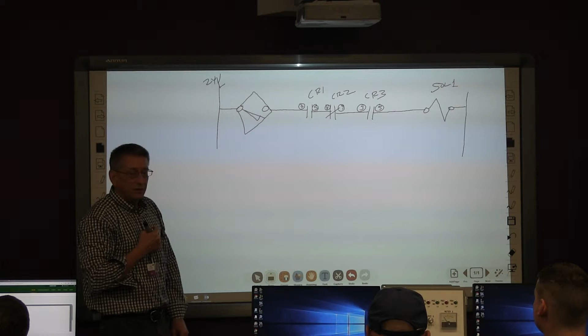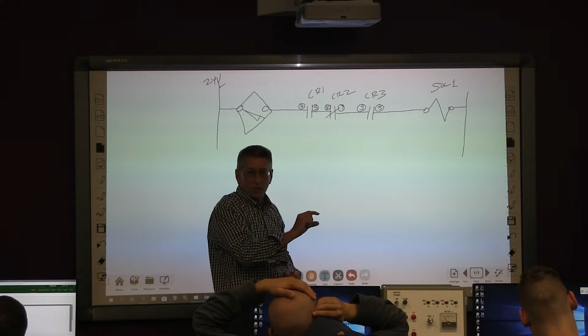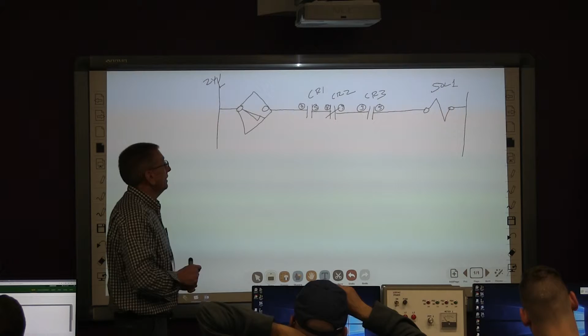Here's the first thing we do. We're already in the electrical panel, right? Where are these relays going to be? In the panel. So you can do a visual observation first - okay, CR3 is energized, you look at it, it's pulled in. Or the light's on if it's a high-speed relay.